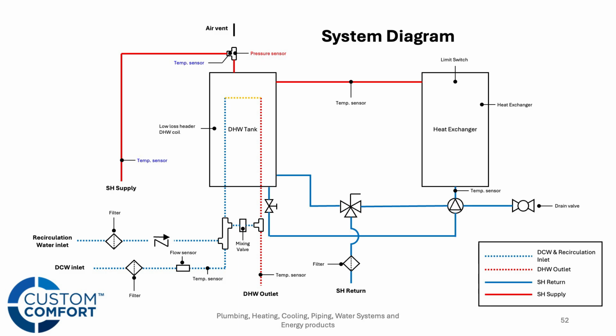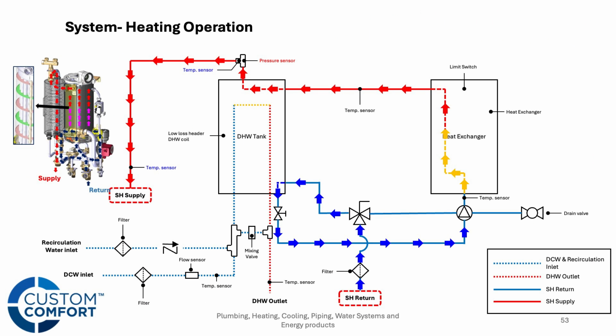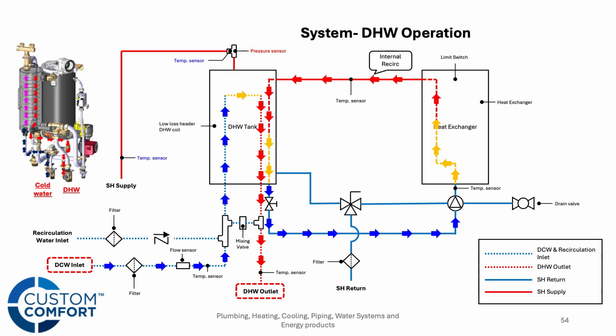You can see a circulator is pushing up through the fire tube heat exchanger. Got that loop there. Another look at it. So heating mode: coming in cold, going out hot. Domestic, same thing: cold water coming in, going up through the coil of that low loss header buffer tank. And as you can see on the heating side, we're circulating there, getting flow through both the fire tube heat exchanger and then the buffer tank.